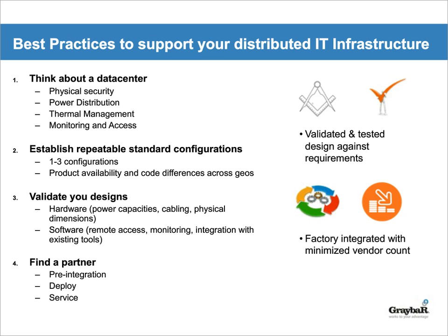Validate your design, and this is very important, right? You're going to be rolling out this equipment to multiple locations. Now, a lot of times you're not going to be there, right? That's going to be done by contractors. So before you finalize your design, bring everything in-house and build it yourself. Look at all the power capacities, look at all the cabling. I mean, cabling seems like it's not important, but it is important, right?